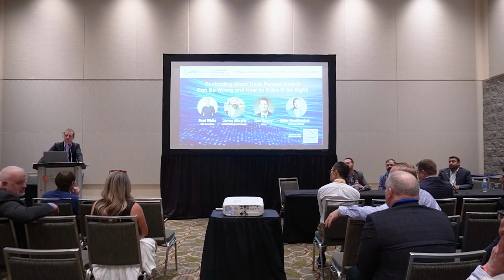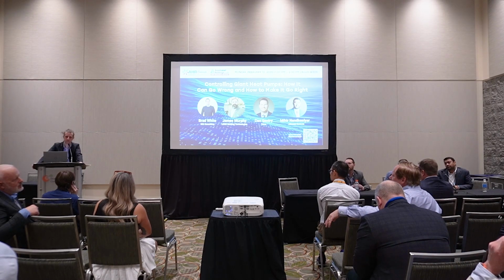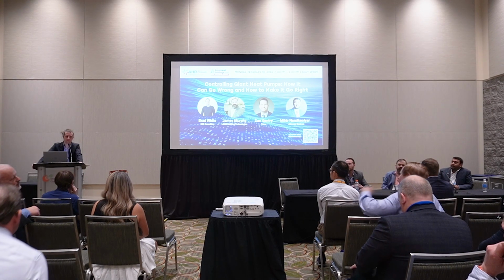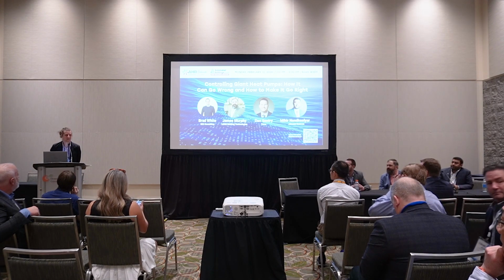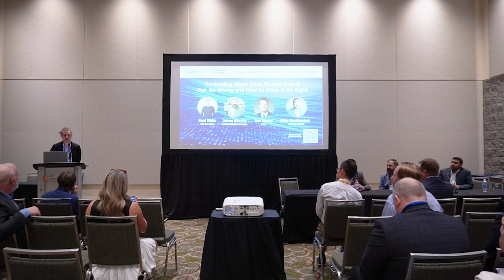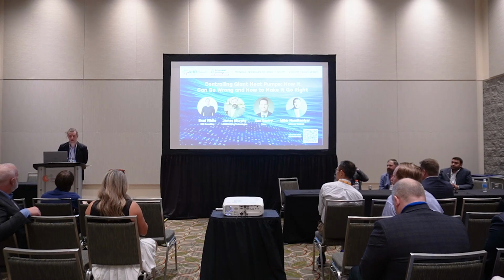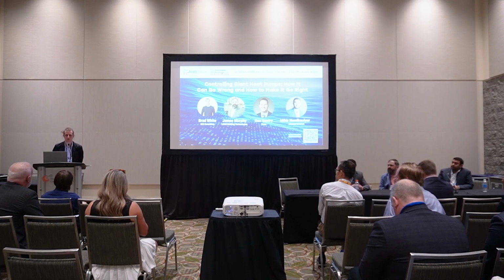But question back there. I'm just curious if you have any specific lessons you've learned on domestic hot water. I think it's a different animal. A lot of what we talked about applies, but we've done a lot of domestic hot water heat pumps, and the big thing there, again, is volume, but you need a lot more. Unless you're going to have a hybrid system, you need a lot of volume compared to a conventional domestic hot water system. You just can't get the same BTUs out of a heat pump. Smaller systems are fine, like an office building, but anything residential, we've done a lot of multi-user residential ones, and they've pretty much all been hybrid systems because there's no other way to do it.